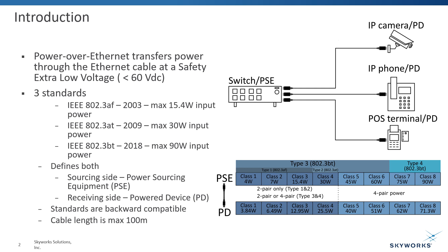The oldest generation of the standard, the IEEE 802.3 AF, limits the maximum power to 15.4 watts. The subsequent generation doubled it to 30 watts, while the newest BT version already allows 90 watts power through the Ethernet cable. The devices are assigned to classes based on their requested power consumption, while the standard limits the length of the cabling to a maximum of 100 meters between the segments. Therefore, the allowable power highly depends on the distance between devices and the assigned class. The figure shows the available power at both sides when maximum cabling is assumed.